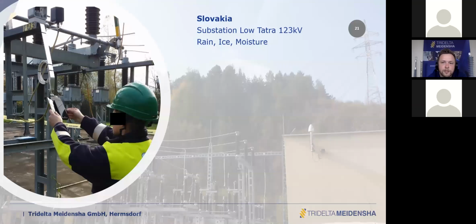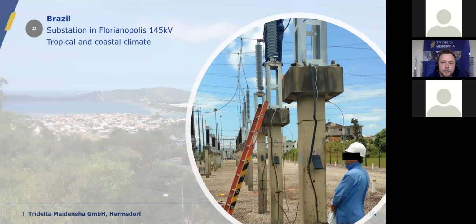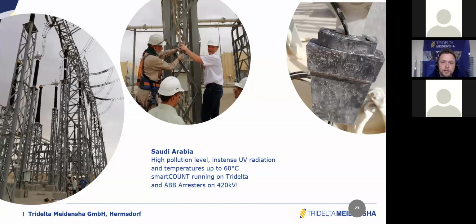We have 2 installations in Slovakia, Low Tatra, 123 kV, and here we have something to do with rain, ice, and moisture with one of our customers and partners, which was a very good cooperation here. Found many things which we had to work on in the device. We have an installation in Brazil, coastal and tropical climate, challenging for surge arresters and for the monitoring system as well. And here we have a very interesting installation in the desert of Saudi Arabia, with high pollution, intense UV radiation, high temperatures. And it's an interesting case because we have the smartCOUNT running on Tridelta surge arresters and ABB surge arresters on the same system.